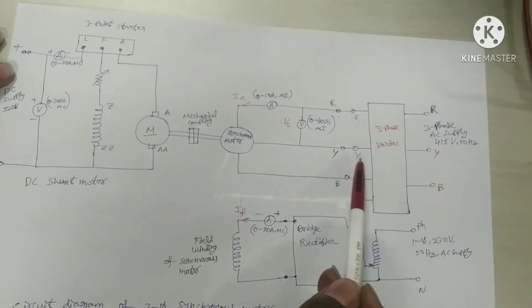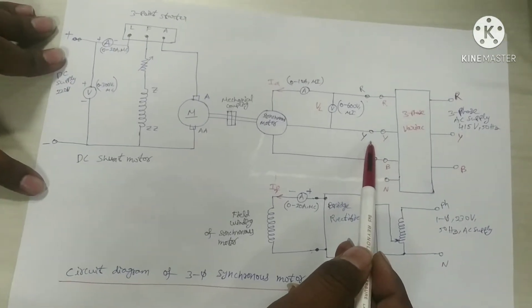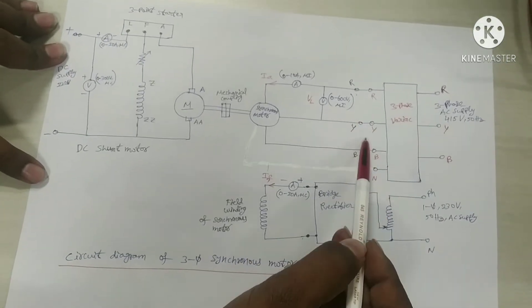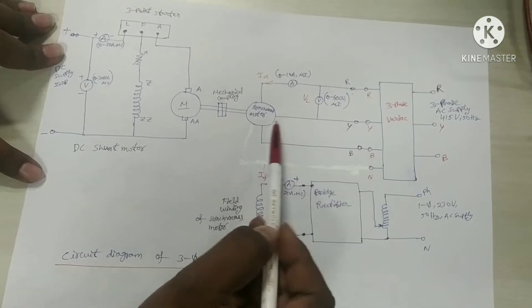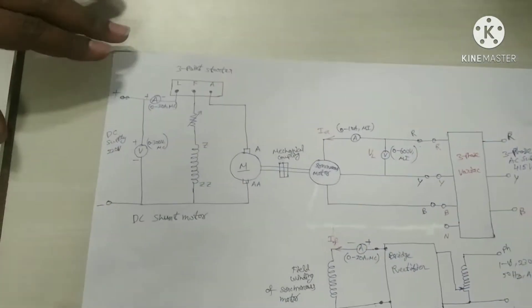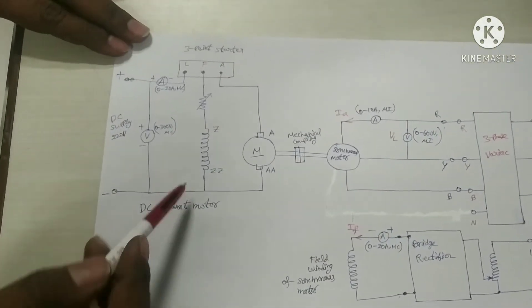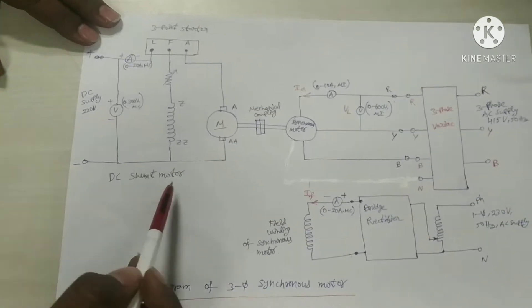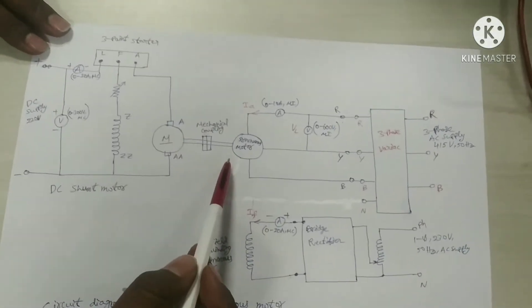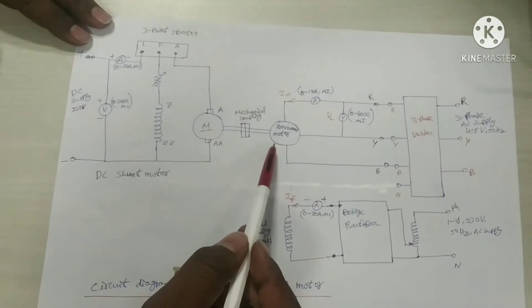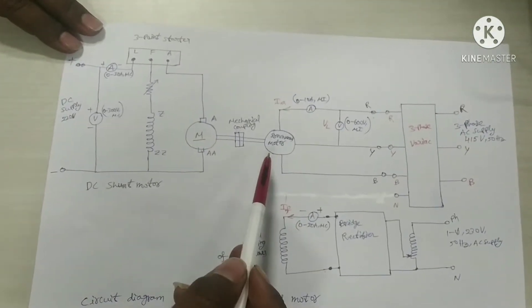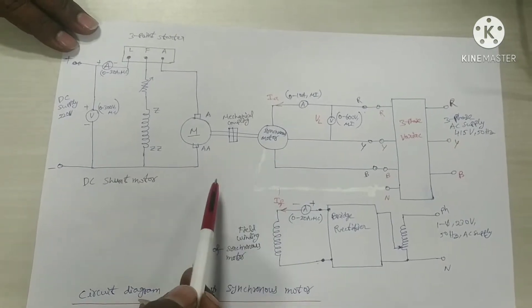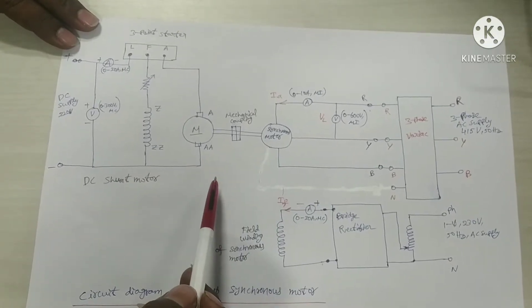By using a 3-phase variac, we are going to give the 3-phase AC supply to the stator winding terminals of the synchronous motor. And by using a DC shunt motor, we are going to start the synchronous motor, because a synchronous motor is not a self-starting motor.